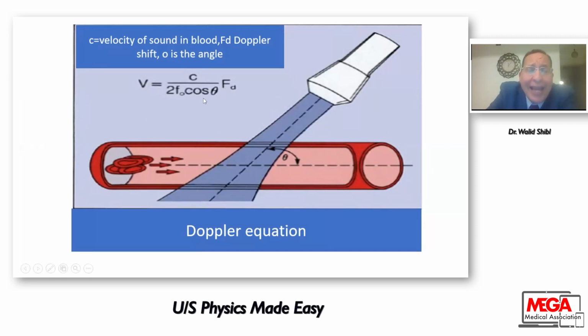So the only rule you have in Doppler is to adjust the angle. You need to make this angle as low as you can. You need to be parallel to the blood flow to get the real velocity. But this is very difficult. So at least, if you use an angle, try to decrease this angle as much as you can. At least in blood vessels, it is up to 60. In cardiac examination, it is 30, decrease to 30, okay? The cosine of the angle 0 is 1, and the best angle is 0, but at least try to decrease the angle as much as you can, and this is your rule.